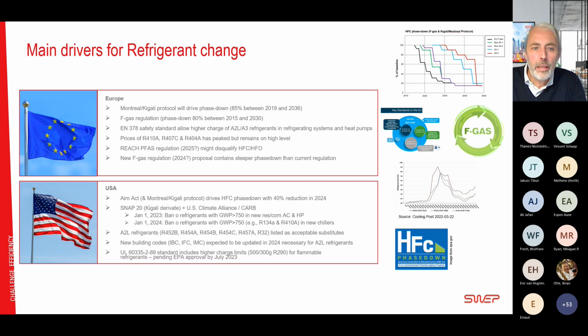We are following the EN 378 safety standard, which allows higher charge of A2L and A3 refrigerants in refrigerating systems and heat pumps. We have also seen that the prices of 410A, 407C, and 404A have peaked, but they still remain at a high level. And we have a small graph down here illustrating this from the cooling post. So around 2018, we had a peak here, and it declined, and now it remains at a fairly high level.